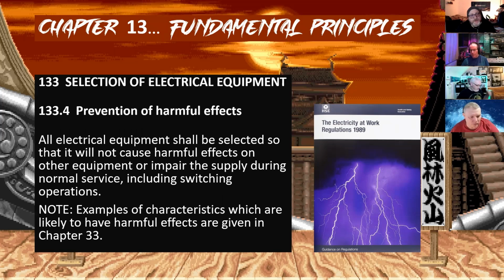Dave, my turn? All right, 133.4 - prevention of harmful effects. All equipment shall be selected so it will not cause harmful effects on other equipment or impair the supply during normal service, which includes a switching operation. Take note, examples of characteristics which are likely to have harmful effects are given in chapter 33, which is the compatibility chapter, isn't it? It is, yep.